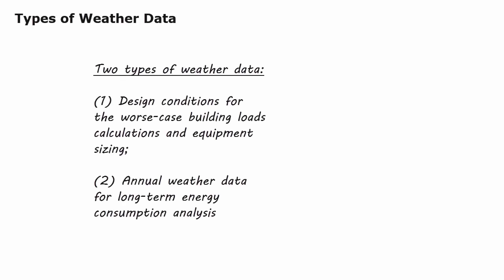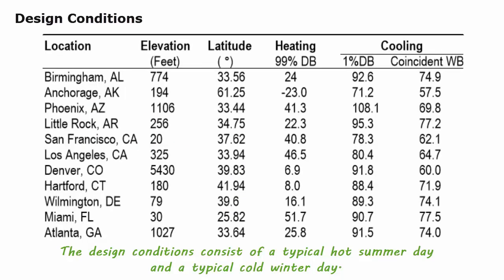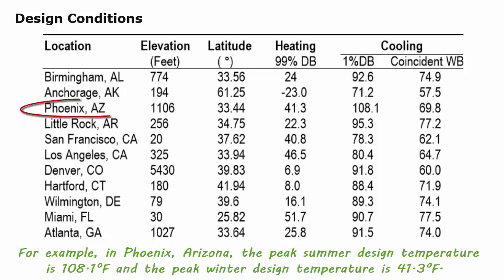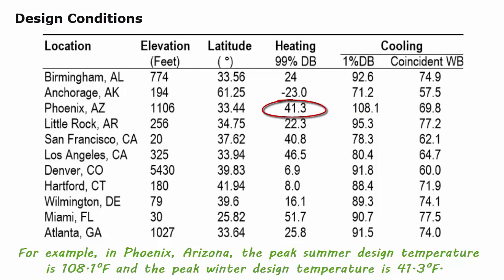Two types of weather data are used in building design. The first is design conditions for worst-case building load calculations and equipment sizing. The second is annual weather data for long-term energy consumption analysis. The design conditions consist of a typical hot summer day and a typical cold winter day, representing the worst-case peak heating and cooling loads the building systems are designed to handle. For example, in Phoenix, Arizona, the peak summer design temperature is 108.1 degrees F, and the peak winter design temperature is 41.3 degrees F.